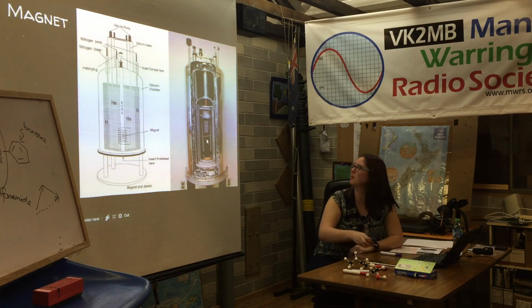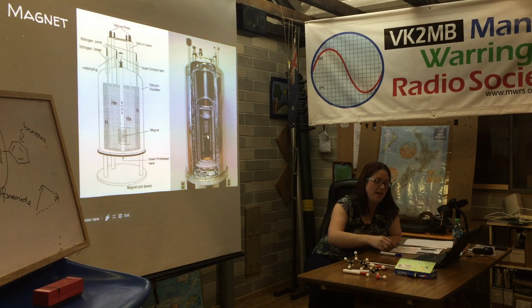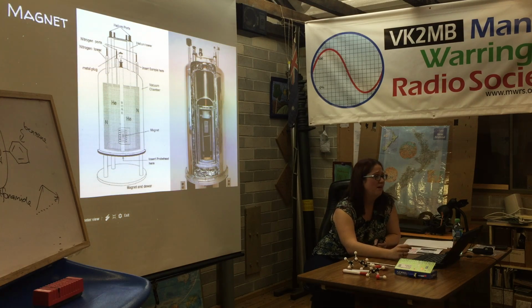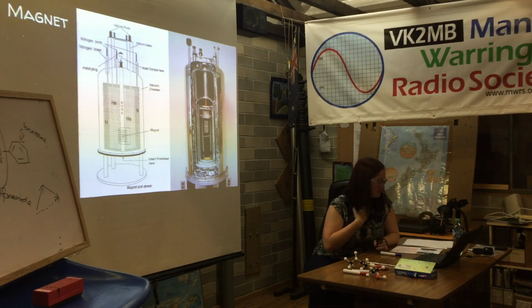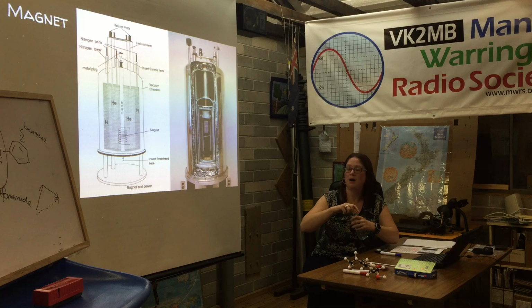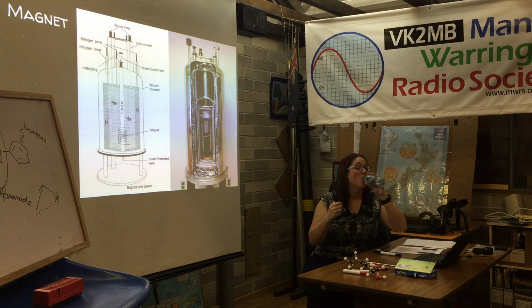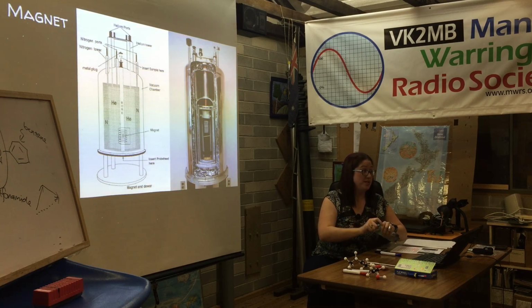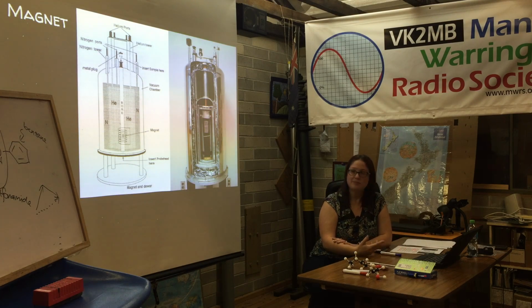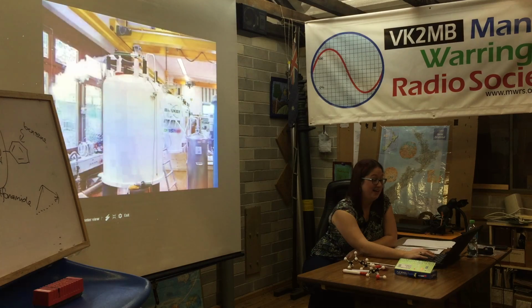But it was only a cryo-shim, so it probably can't be seen, but I can use the mouse, I suppose. There are some windings that are taped on that are not going that way around, they're going that way. And those windings are cryo-shims. You may be familiar with the word shim in terms of a lump of metal that you would introduce in order to distort a magnetic field. The term has carried on, but these cryo-shims are extra coils in different directions that are used to fine-tune the homogeneity of the field on installation. And if one of those quenches, then you get some symptoms which are very similar to a quench, but it doesn't necessarily develop into a full-blown quench. So you get excessive helium boil-off, you get some icing on the turrets, but it doesn't carry on to that full chain reaction. At least you hope it doesn't.